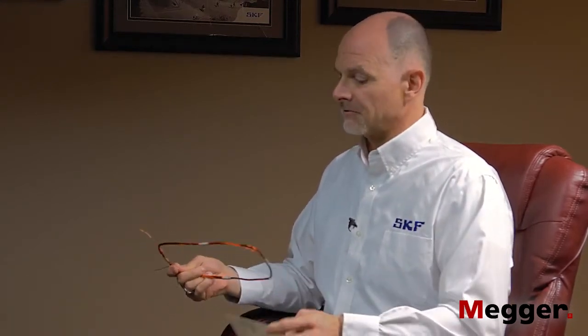What you're doing is putting a DC voltage across your coil. So there's no voltage difference from turn to turn. So it's basically all one big piece of copper. All right, so you're not checking for problems between turns at all with any kind of DC test, of which a megohm test is the most common.